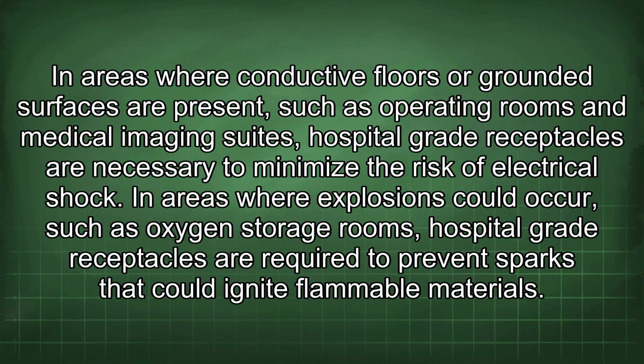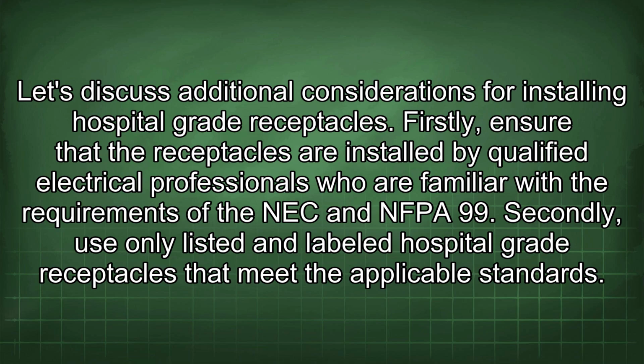In areas where conductive floors or grounded surfaces are present, such as operating rooms and medical imaging suites, hospital-grade receptacles are necessary to minimize the risk of electrical shock. In areas where explosions could occur, such as oxygen storage rooms, hospital-grade receptacles are required to prevent sparks that could ignite flammable materials. Let's discuss additional considerations for installing hospital-grade receptacles.